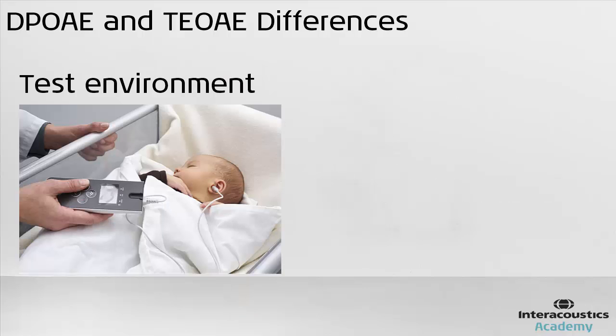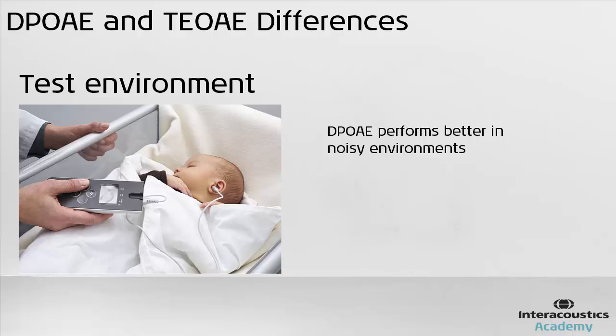In noisy environments, DPOAE will perform better and will still obtain otoacoustic emissions while TEOAE in some occasions cannot. Still, a quiet environment gives by far the best performance for both screening methods.